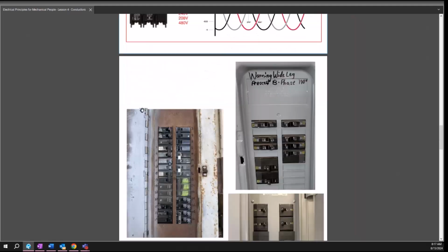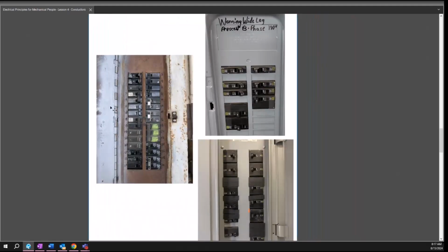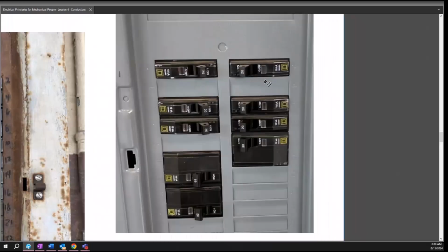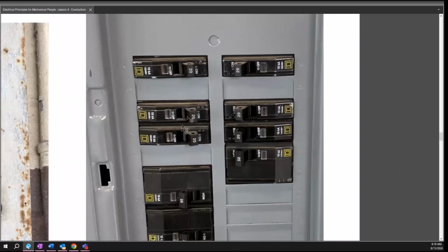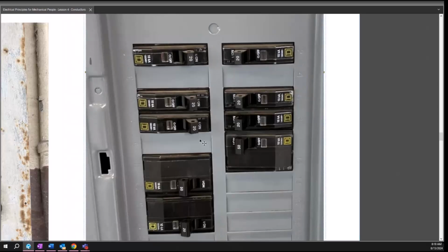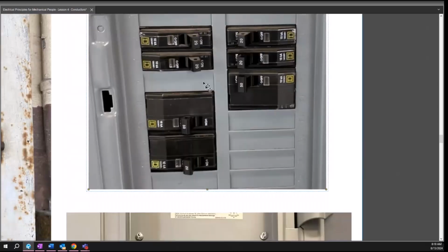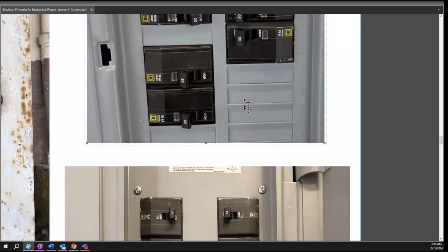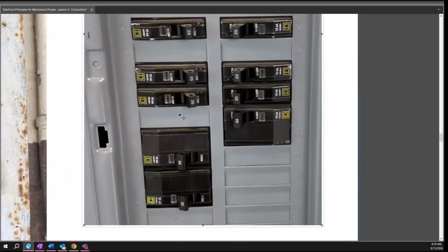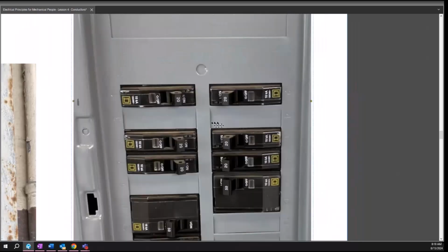So here are a couple of panel boards I've come across. You can always quickly identify something that may be 240 high leg when you have random breakers being skipped, especially when you have two singles and a skip. The reason they didn't put breakers here is because you'd be reading 208 to ground, so you couldn't put a receptacle on this one, or this one, or that one, or that one. All of these would be blank if these were all single poles.